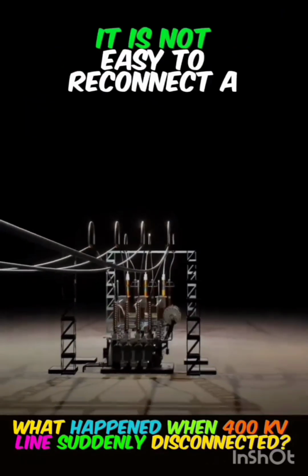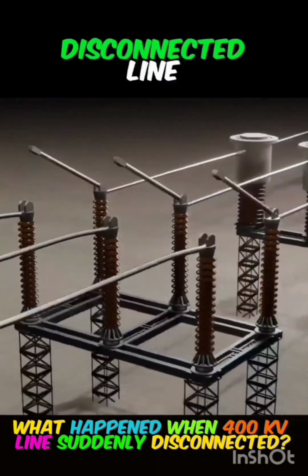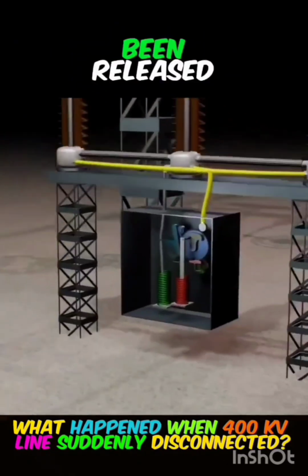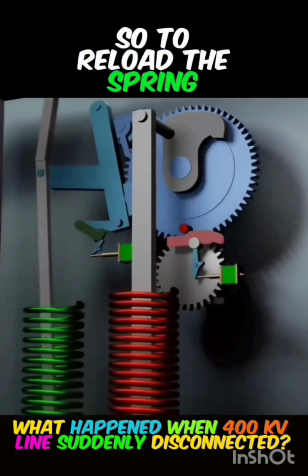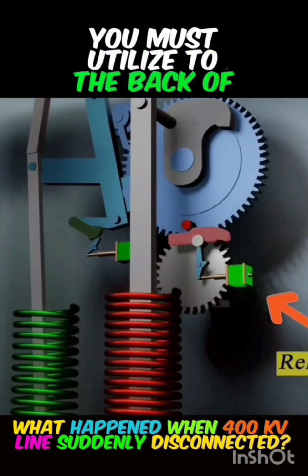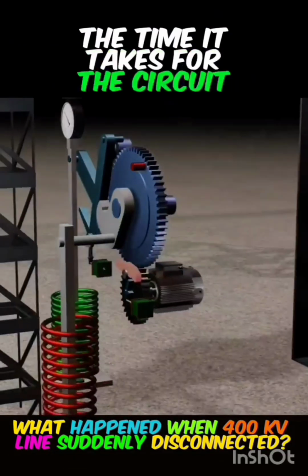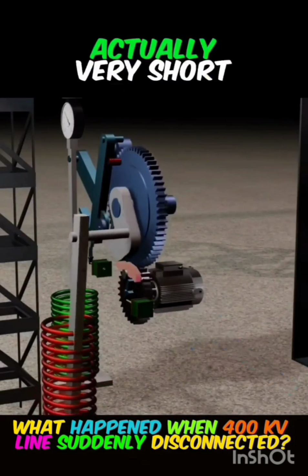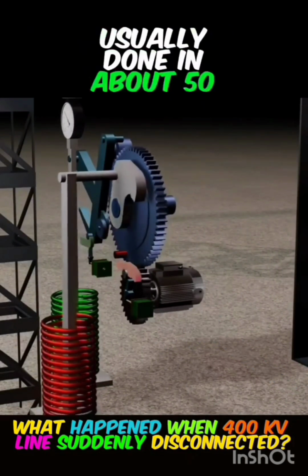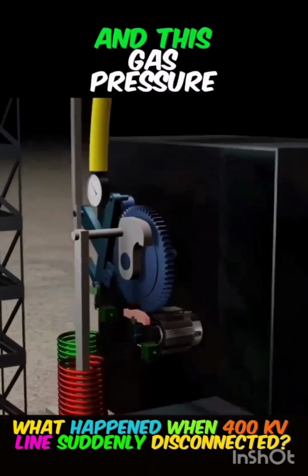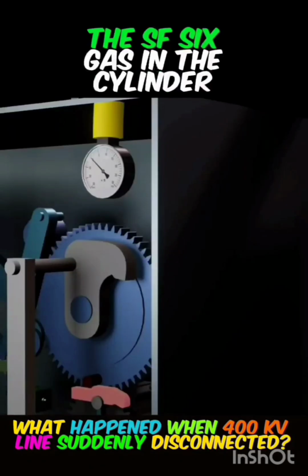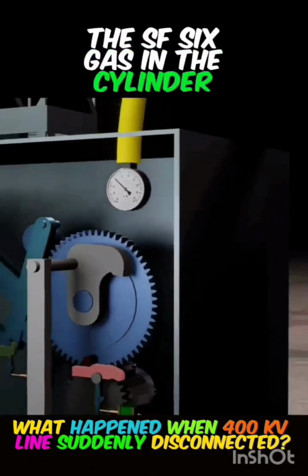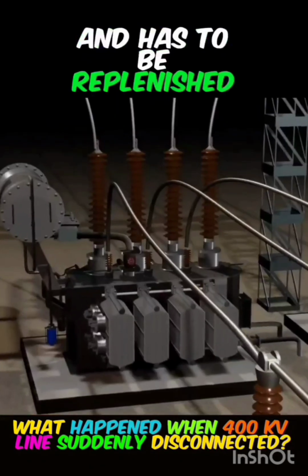It is not easy to reconnect a disconnected line because the spring force has been released, so to reload the spring, you must use the motor at the back. The time it takes for the circuit breaker to open and close is actually very short, usually done in about 50 milliseconds. And this gas pressure gauge monitors the SF6 gas in the cylinder above, and it has to be replenished when the pressure is found to be low.